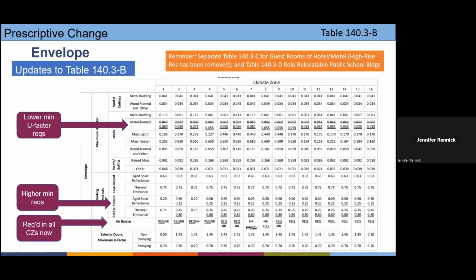And now, for example, climate zone 5 in San Luis Obispo, or climate zone 4, got a U factor of 0.055. And if you're going to use a metal framed wall to get that to comply prescriptively, you'd want to use the equivalent of a 2x6 metal framed wall. You're going to want to use the spacing 24 inches on center, and to fill that cavity with a high density batt insulation or other material that's going to give you your highest density. So you might have an R21, could get up to an R23 in there. And then you're going to clad the outside of that with like an R12 rigid insulation. Wow. So yeah, that could be 2 or 3 inches.